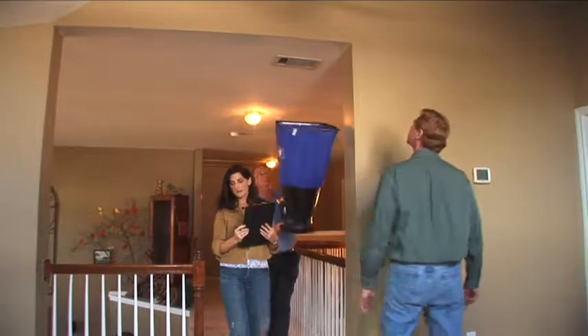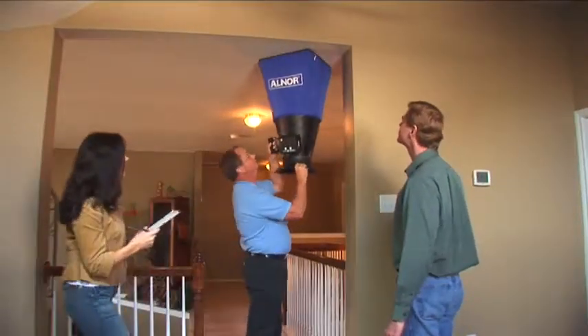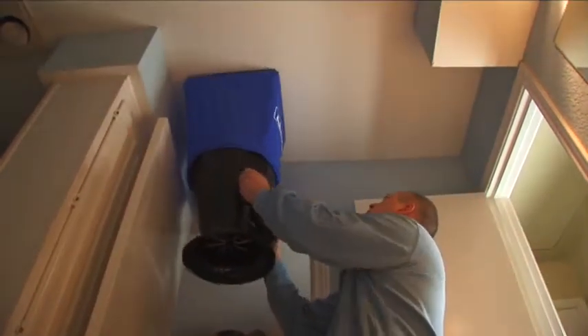Your contractor can measure the duct leakage in your system and compare it to what it should be under current new construction codes. This testing can be done to diagnose the extent of the problem and to confirm that leaks were actually sealed after repair.